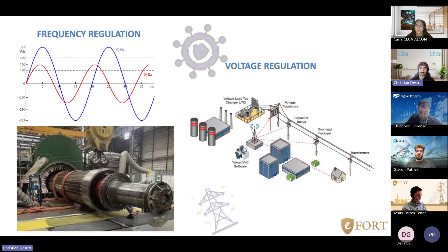and a mechanism to guarantee continuity of service—an emergency management tool. However, operating in islanded mode requires local balance between generation and load, autonomous control of frequency and voltage, coordination between inverters and storage systems, and adaptive protective strategies. When generation is highly distributed among prosumers and small plants, centralized management becomes less effective. That is where distributed control systems, predictive algorithms, agent-based solutions, and multi-agent coordination strategies become relevant. The objective is not only to prevent system collapse, but to make the grid adaptive, capable of dynamic reconfiguration, isolation when necessary, and local stability maintenance.